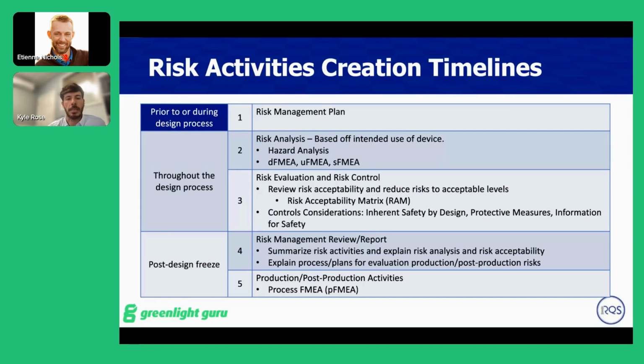Similar to what I discussed on the design side is when to start these activities. Similar answer as the initial question with the design: very early in your device. Do you want to start to have your risk management plan and your hazard analysis? The hazard analysis is really key, similar to how the user needs and inputs are key, because you want to identify what standards and what key risks are part of your device, because it's going to change drastically from a class 1 device to a class 3 device, a hardware device to a software device or a mechanical sterile device.